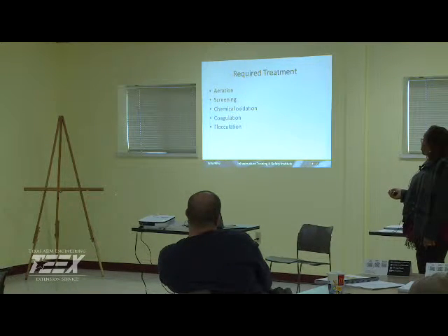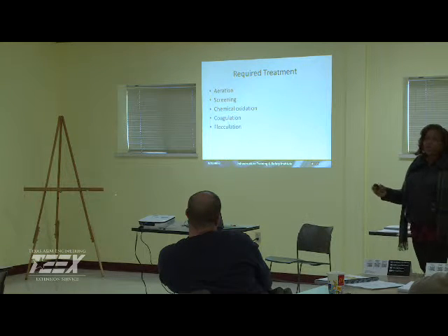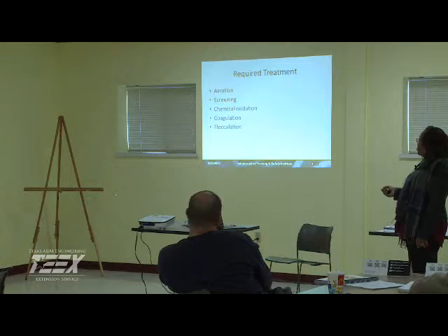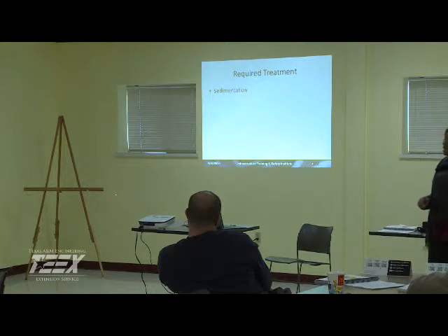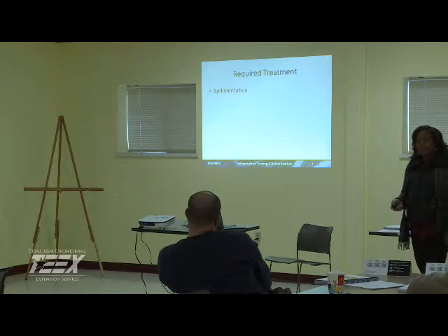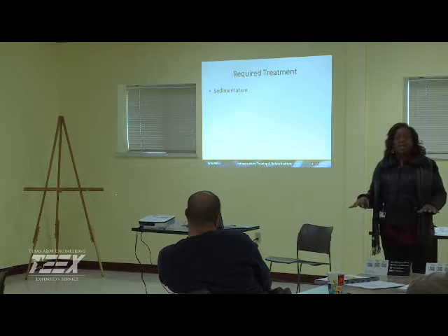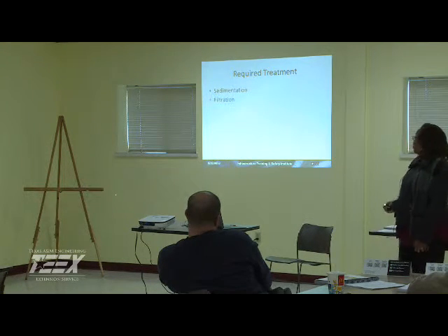Coagulation, of course, is a process of adding those chemicals for particles to clot together and form floc, and then sedimentation. So we have aeration, screening, chemical oxidation, coagulation, flocculation. Sedimentation is where we provide a quiet area, and heavier solids settle out by gravity, and after sedimentation, filtration.